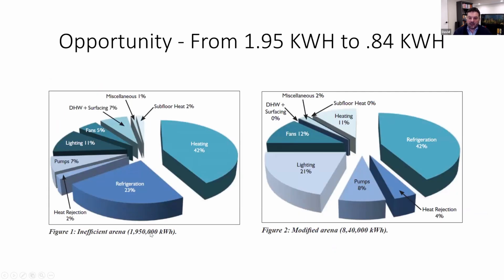There's a study done a few years ago looking at a rink before and after a heat recovery plant was installed. The average ice rink uses about 2 million kilowatt-hours per year, seasonally, with 42% of that use in heating. After the EcoChill heat recovery plant was installed, the refrigeration portion of the pie went from 23 to 42%, but the total kilowatt usage was cut in half.